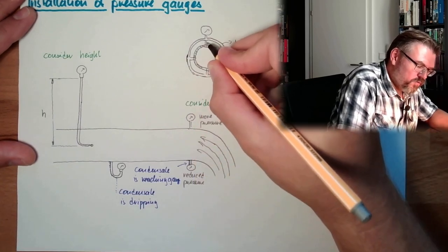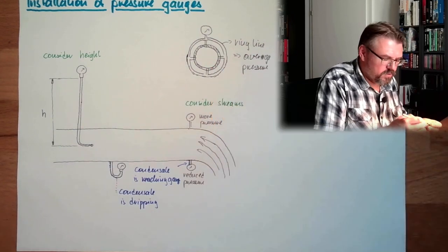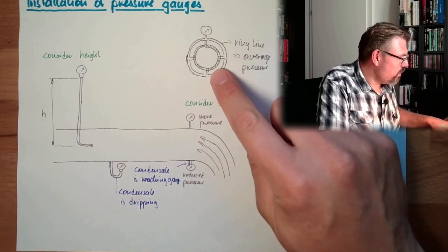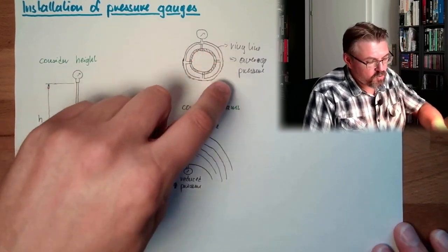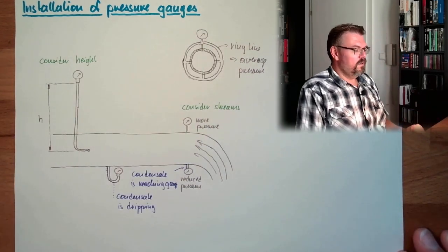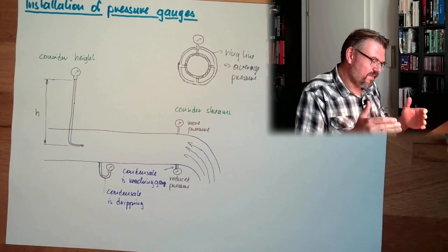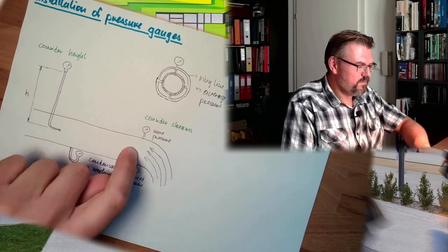Usually then there are also valves here to shut off and so on, but this is expensive. If you don't want to do this, if you have another better place, put it in a better place. If you cannot avoid, you could use it like that, that there is a ring line which is distributing the pressure from the different pressure measurement points. That are typical things which needs to be considered when installing pressure gauges somewhere. Consider streams, consider the height, consider condensating possibility. Actually that's it.